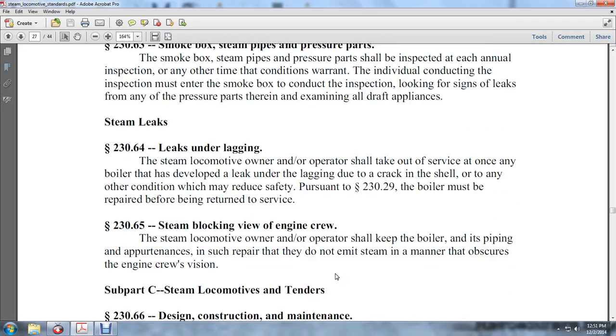Steam locomotives — steam leaks under lagging: a steam locomotive owner and operator shall take the boiler out of service once it has developed a leak under the lagging due to a crack in the shell or any other condition which may reduce safety. Pursuant to Section 230-29, the boiler must be repaired before being returned to service.